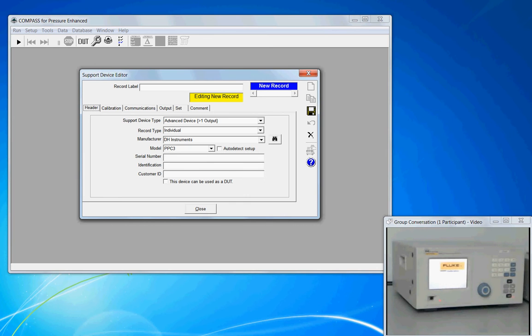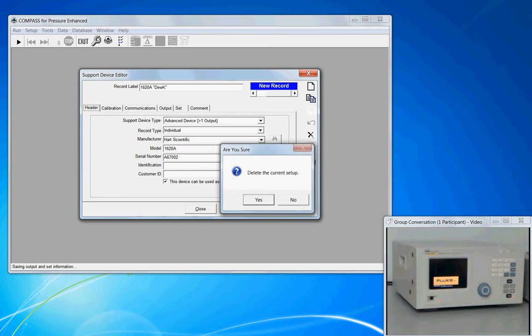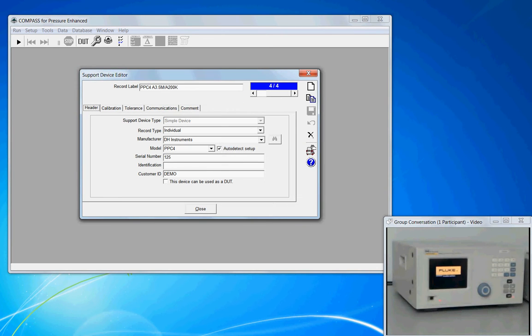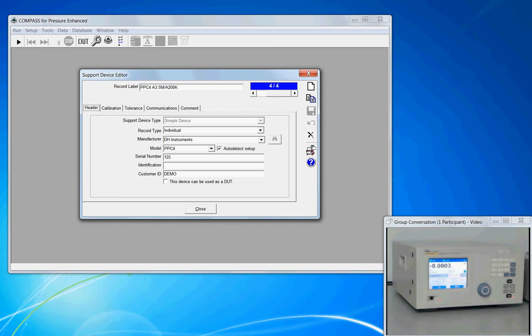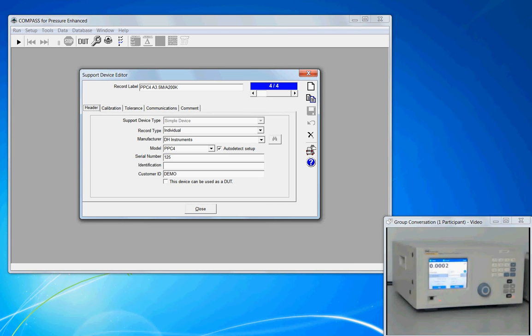I'm going to back out of this record and go back to the existing record. Okay, so the PPC-4 is a Fluke Calibration product, and most of the pressure products produced by Fluke Calibration have a very nice feature that simplifies your responsibility for setting up the device, and that's called Auto-Detect. Here in the middle of the page, we have Auto-Detect Setup, and by checking this box...